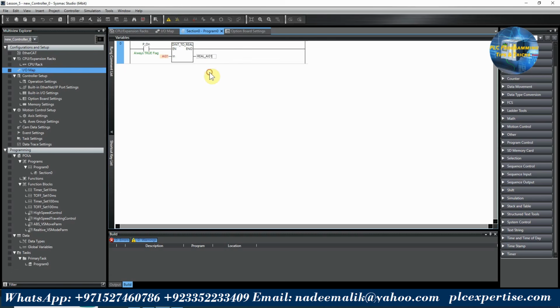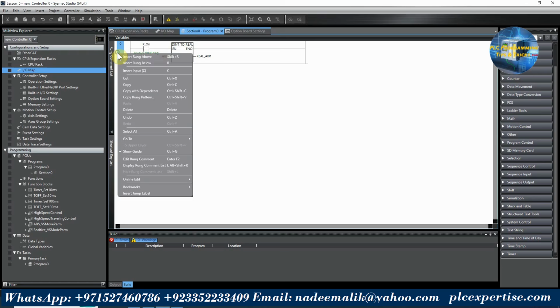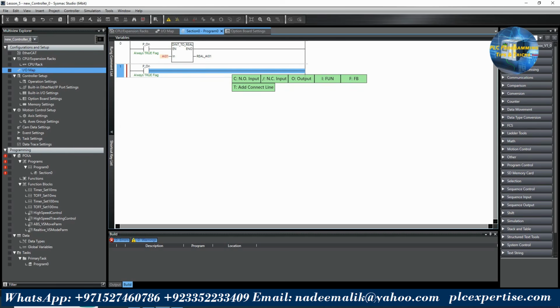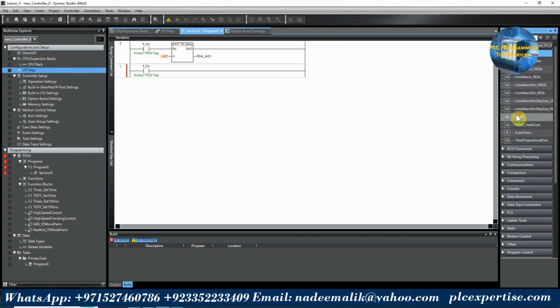Now to store the real value, at the output side, we will assign here AI01's real value. Next, we will insert here another rung. Next, we will insert here another NO contact input and assign here the same P_on flag. Next, to scale this raw value, which is in real format, we have to use a scaling block. We can find this block in the analog conversion, and here we will use this scale transformation block.